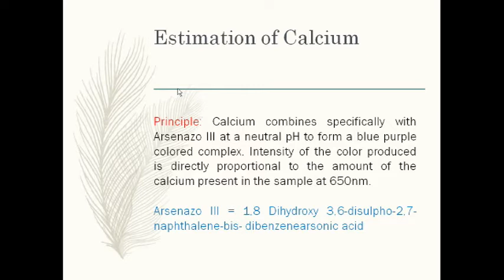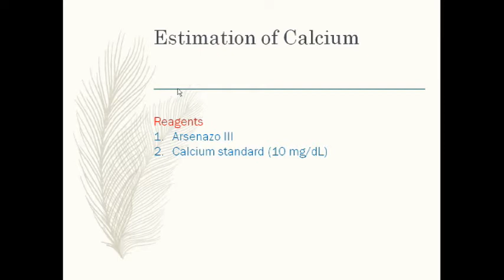The reagents are composed of Arsenazo 3 reagent and calcium standard. The standard has a concentration of 10 milligram per 100 ml. And the procedure is as follows. You take 3 test tubes, label them as blank, standard and test as a sample. You pipette 25 microliters of distilled water into the blank and 25 microliters of the calcium standard, which is provided in the bottle labeled as 10 milligram per deciliter, and you pipette 25 microliters of the serum which you have collected in the heparinized sample.